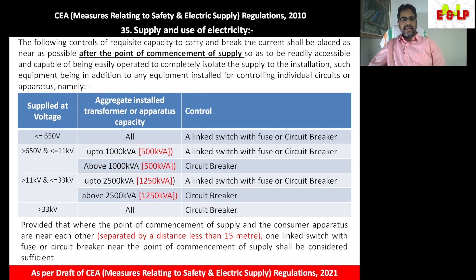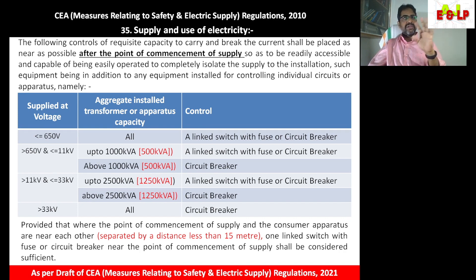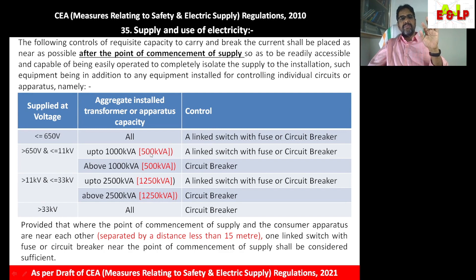Another thing to note — refer to the red color — is that a draft safety regulation was released in 2021, though it has not yet been officially released. As per this draft regulation, in the first category (650V–11kV), the transformer rating limit changes from 1000 KVA to 500 KVA. And in the second category (11kV–33kV), it changes from 2500 KVA to 1250 KVA.